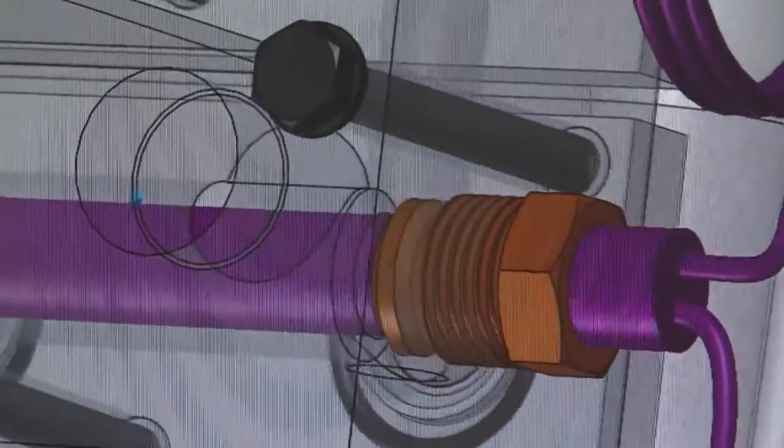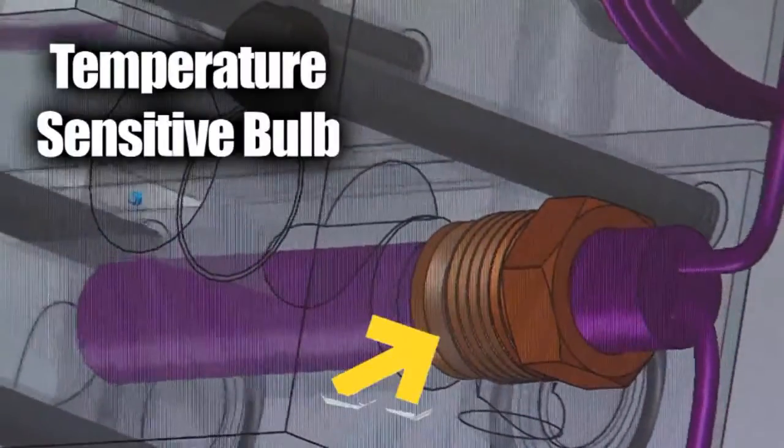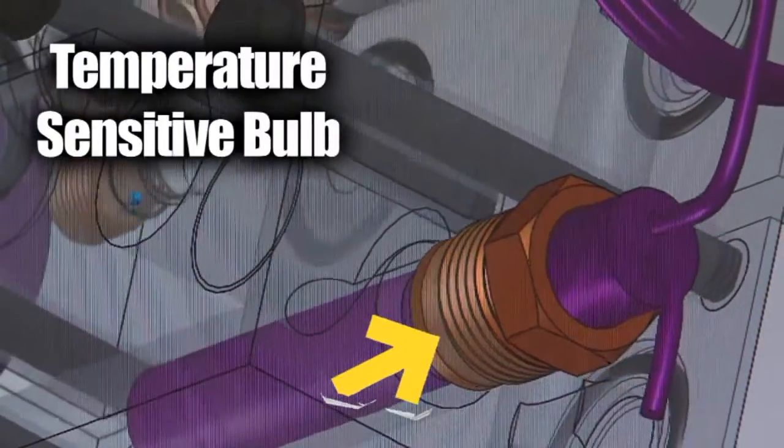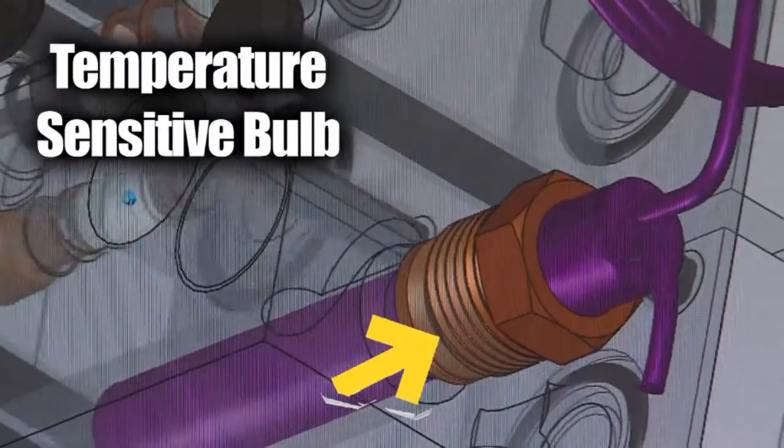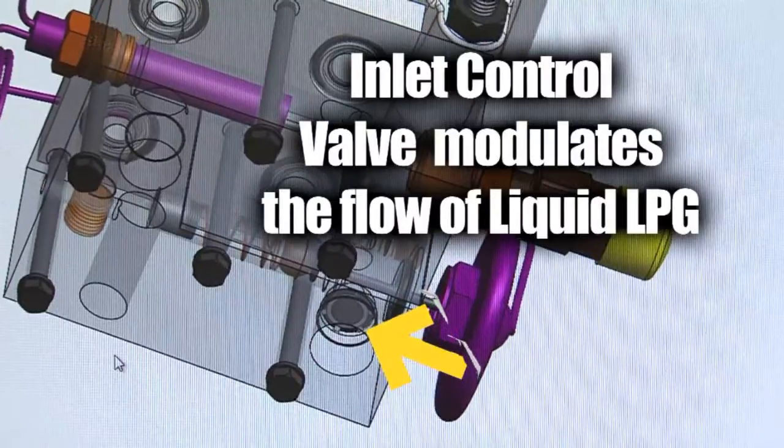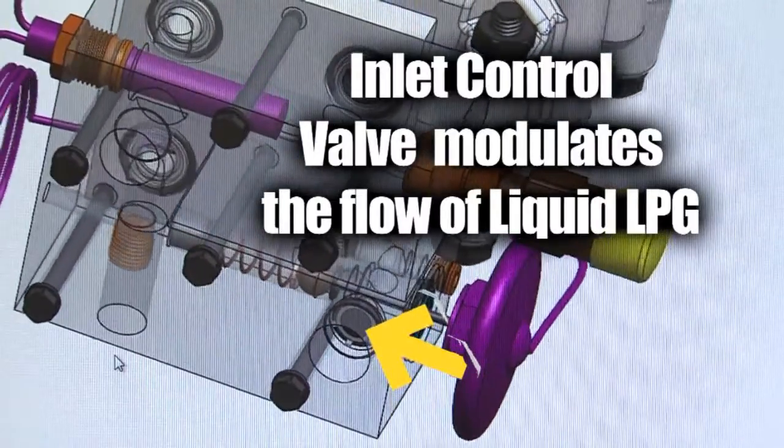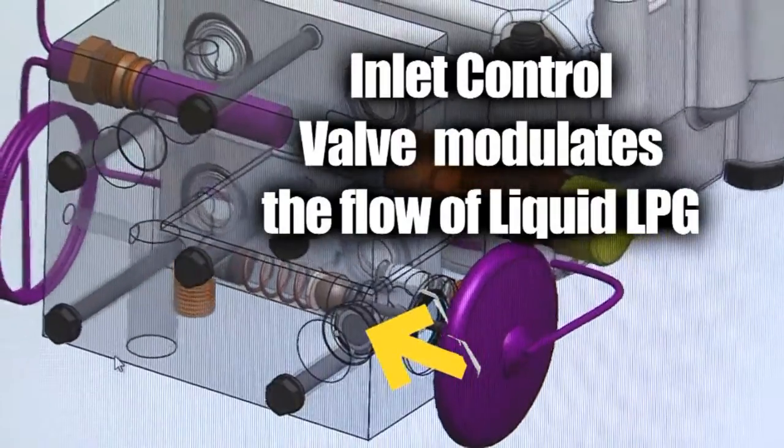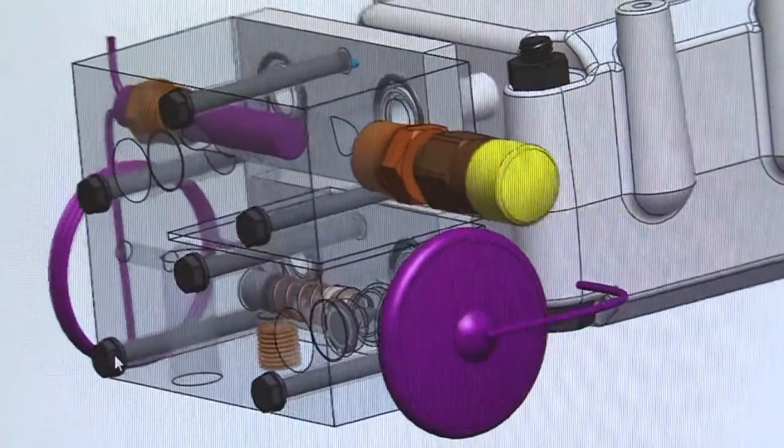The temperature of the LPG vapor exiting Zimmer is monitored by a temperature sensitive bulb. This bulb provides feedback to Zimmer's inlet control valve. The inlet control valve then modulates the flow of liquid LPG into the vaporizer relative to the vapor temperature of the exiting LPG.